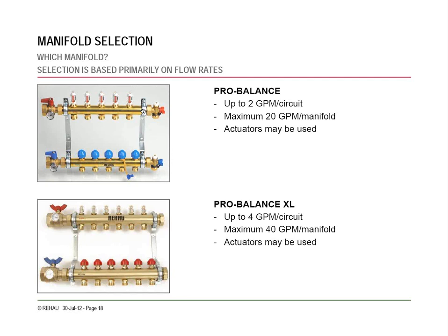The other nice thing about these REHAU ones specifically is you can completely isolate each loop. So if you ever had a problem with one or you needed to purge and everything, you can completely isolate it at the flow gauge and at the balancing valve at the bottom. And then they have the air valves on the end. That's pretty common for all manifolds, the drain valves and supply and return.